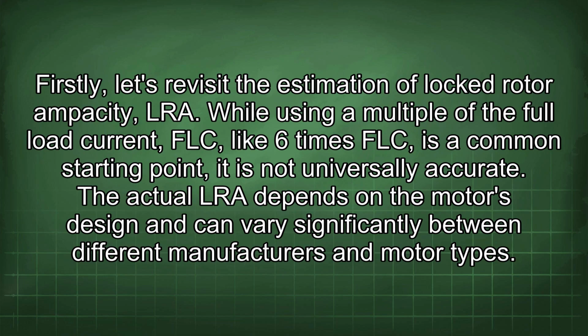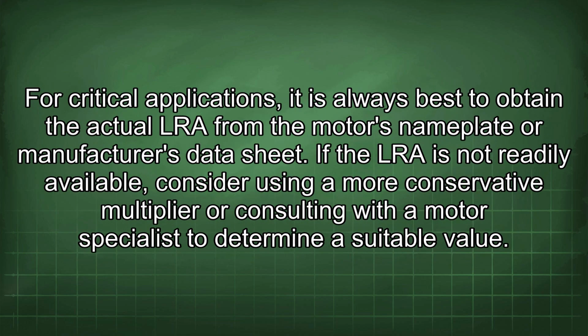Firstly, let's revisit the estimation of locked rotor ampacity, LRA. While using a multiple of the full load current, FLC, like 6 times FLC, is a common starting point, it is not universally accurate. The actual LRA depends on the motor's design and can vary significantly between different manufacturers and motor types. For critical applications, it is always best to obtain the actual LRA from the motor's nameplate or manufacturer's data sheet. If the LRA is not readily available, consider using a more conservative multiplier or consulting with a motor specialist to determine a suitable value.